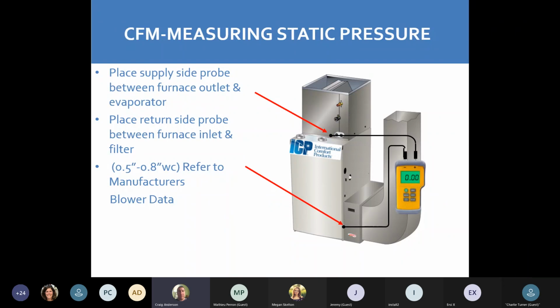It's going to tell you also if your filter's bad, your ductwork's bad, your coil's blocked. We need to make sure that we're getting the proper airflow. If you're getting the proper airflow, static pressure is built into the furnace. It's going to tell you on the side of the furnace on the rating plate what your static pressure should be for that unit. 0.5 to 0.8 inches water column is fantastic. And that's the reading most of them you'll see out there. If you're getting up over the 0.8, if you're getting into 1.2s, 1.4s, you have ductwork problems, or you have a blocked coil, or you have a filter issue. The motor is going to die.